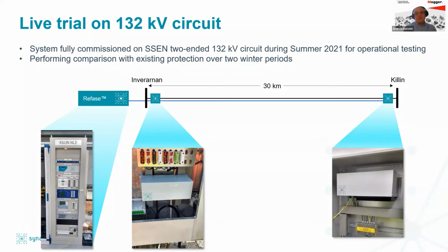This whole system is in principle a merging unit, so it has a certain transfer performance, and that may not be matched by the protection relays, which have their own algorithm based on the transfer performance of the analog input card and current transformer, so it can be slightly different.